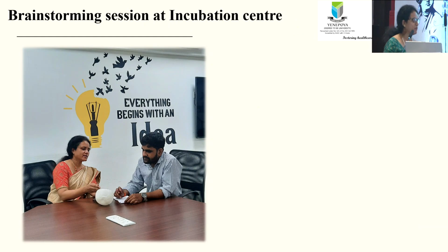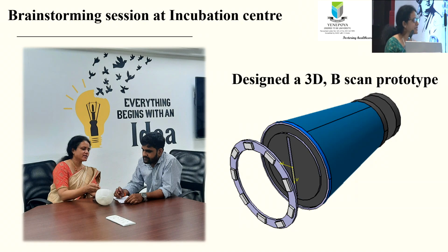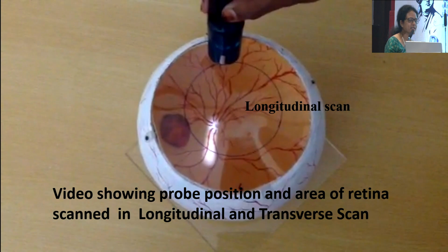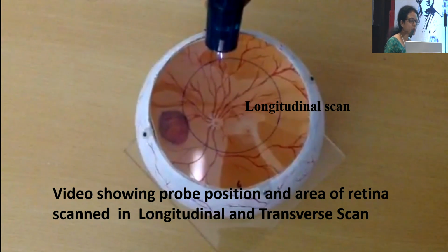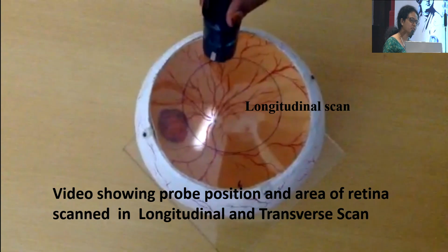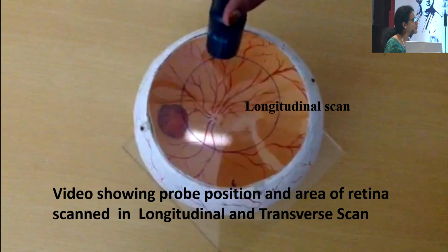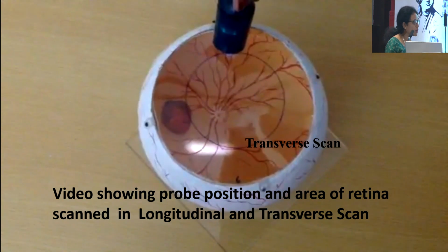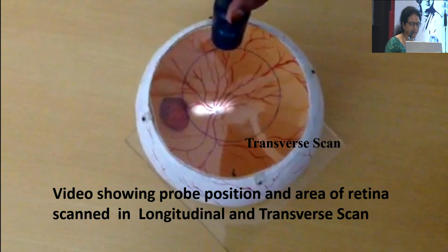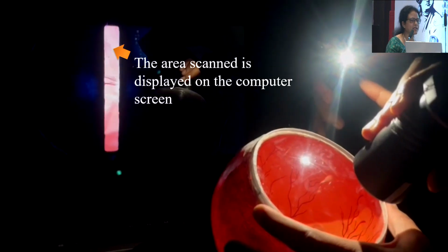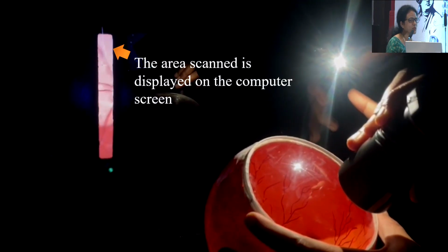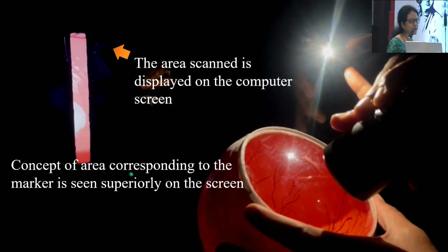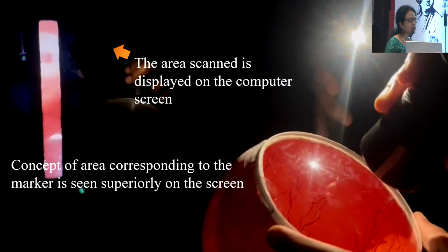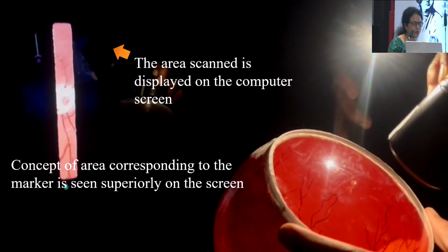We wanted to refine the B-scan, so that is when we designed a 3D B-scan prototype, and this is what we got. You can see this video which shows the positioning of the probe for a longitudinal scan. It's so beautiful to see that the student can also visualize the area of the retina being scanned for these longitudinal, transverse and axial scans. So the learning becomes very simple. The interesting feature of this B-scan prototype is that whatever is being scanned is also captured on the screen. So the students also understand the concept of the area corresponding to the marker being seen superiorly on the screen.